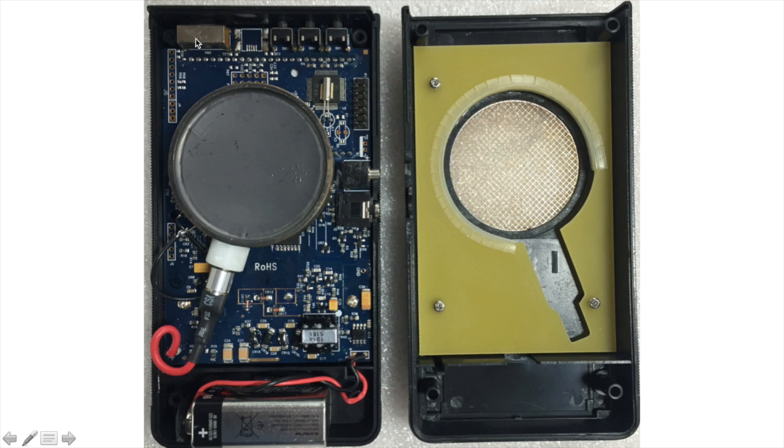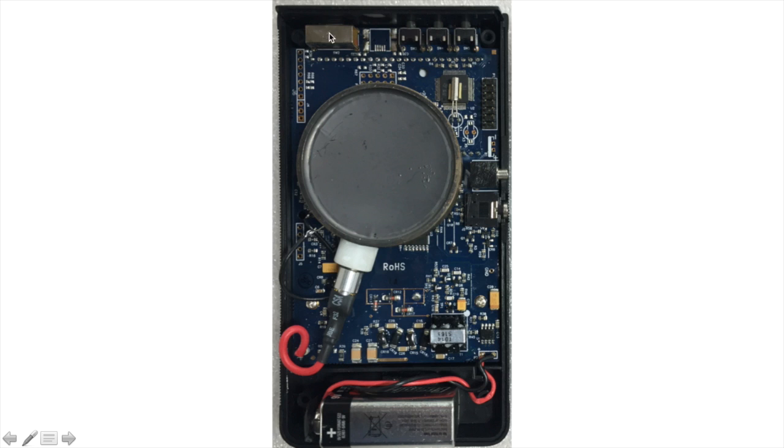This switch here is, let's look at more detail here. This switch is a timer. You have a setting, plus or minus switch when you're programming the unit, and there's looks like a USB connector there that's not mounted. The processor, which is the main smarts of this device, with the crystal over there. These two audio jack connectors here allow you to export the signal and also do calibration. The transformer and this unit here is the high voltage using the ladder of capacitors and diodes here to create the high voltage that then powers the GM tube. And there is 9 volt battery.